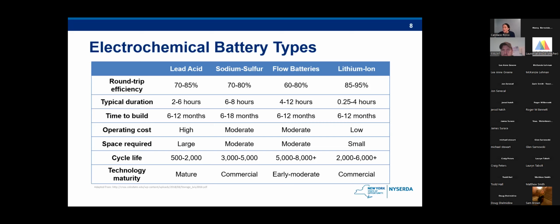So you can see in the chart that lithium ion tend to have a higher round trip efficiency than other types. That means less energy is lost in the storage process. The typical duration is pretty standard, as well as the time to build. The operating cost for lithium ion is low, and the cost of batteries has fallen probably by, I think, 90% in the past 3 decades, and they require limited maintenance during their lifetime. And they also have a very long cycle life. The cycle life of batteries is the number of charge and discharge cycles that the battery can complete before losing performance. So having that high cycle life is definitely a positive. You can see from the chart that these are some of the reasons why lithium ion batteries are really taking off. And this isn't shown on the chart, but different chemistries also present different safety considerations. Those concerns are typically addressed through the New York State Code and the standards.